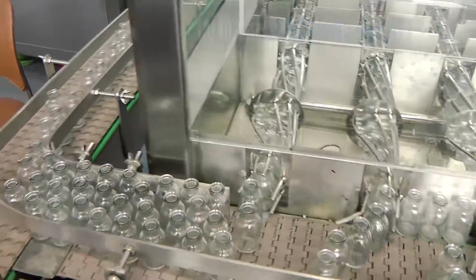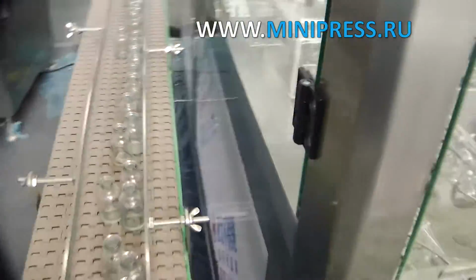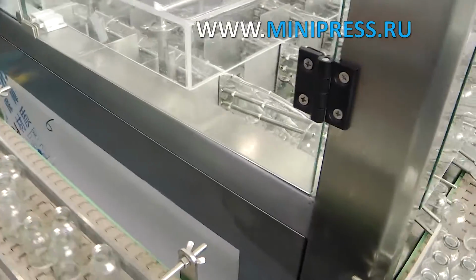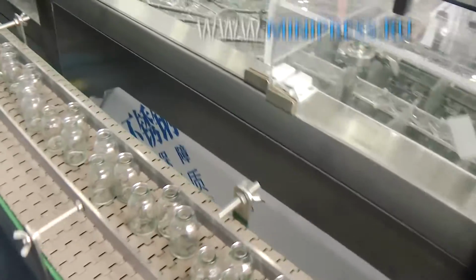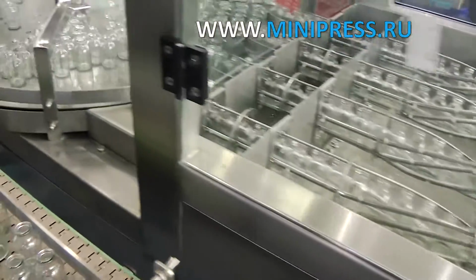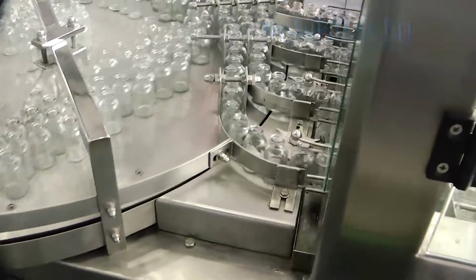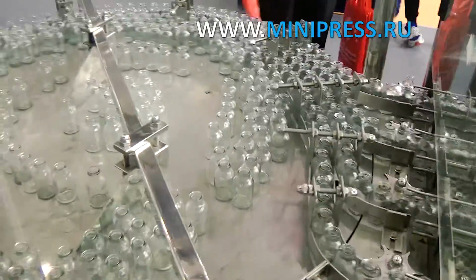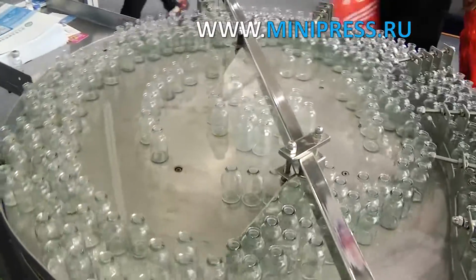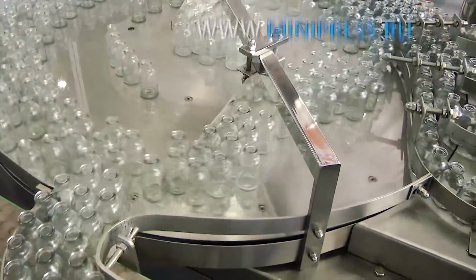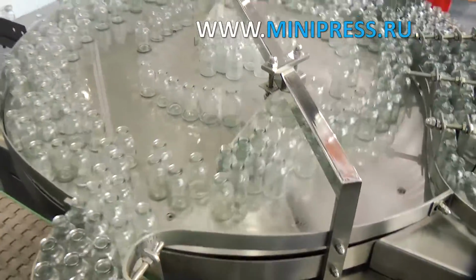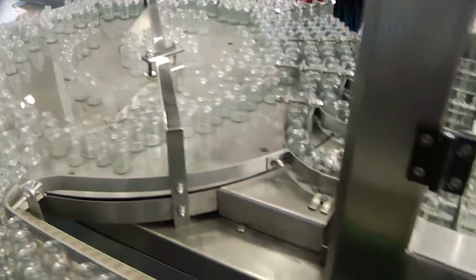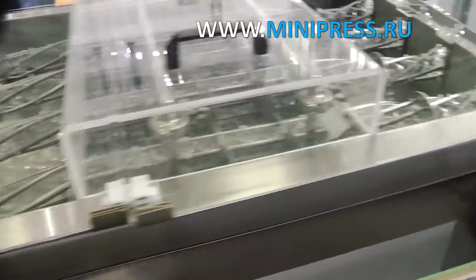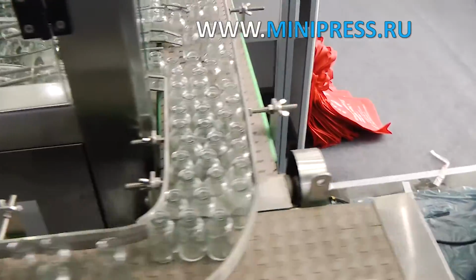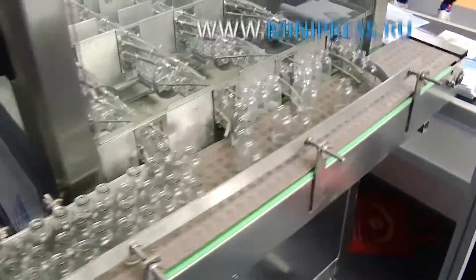After installation and adjustment of equipment, we were able to assess its quality. The equipment is made of stainless steel. The working area of the machine was covered with plastic shields to prevent external influences on the washing process. Process control is automatic with the help of a display. The equipment consists of a metal trough for orientation of the vials, 2 rings with holes to hold the vials, a washing zone, where the vials are directly washed and sterilized. The pressure of water and rinsing air is monitored by manometers.